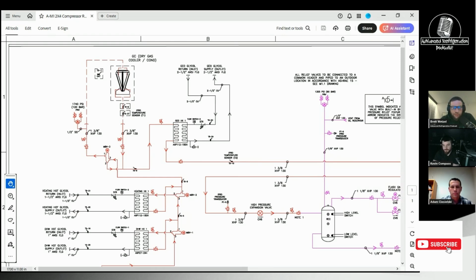Yeah, that's why I like it. Some manufacturers are extremely proprietary about how things are supposed to be. I like the fact that you guys give a cut sheet with every single rack, which shows the sequence of operation and how everything's supposed to be. You give the set points for the iPro controller and the set points for the VFD. So there's no guesswork. You're not trying to keep it a secret, because you probably have the mentality that if the technician doesn't know how it's supposed to be programmed, how are they supposed to fix it. So the fact that you give all that up front, and you probably make sure the fans aren't overlapping with the low pressure set point. Kevin, we talked about this before. It's comparable to having the fan cycling and a holdback valve going on at the same time.